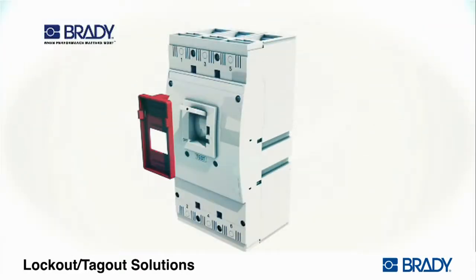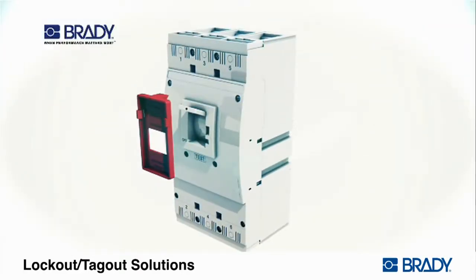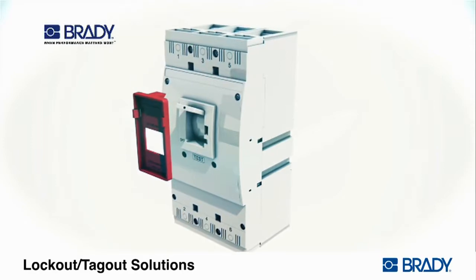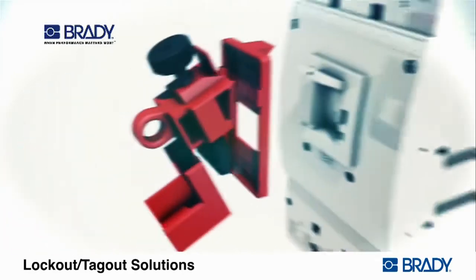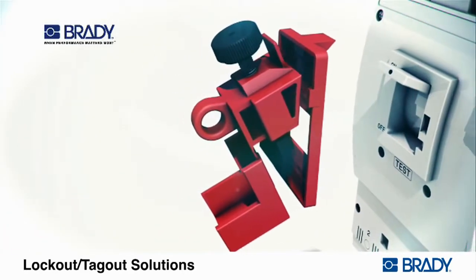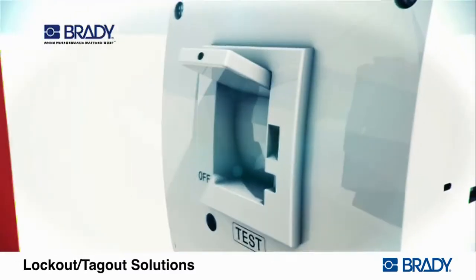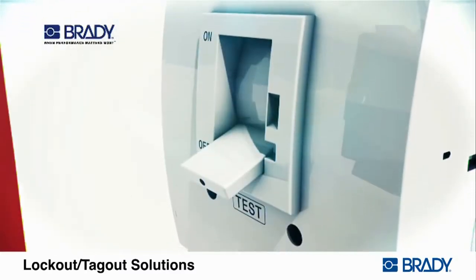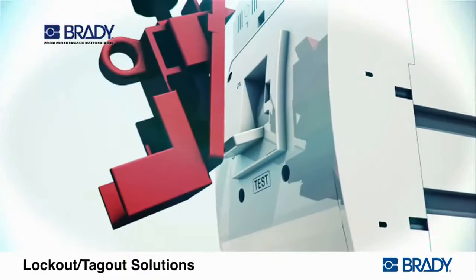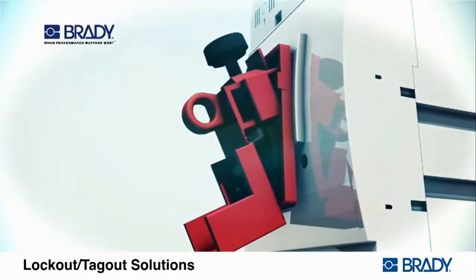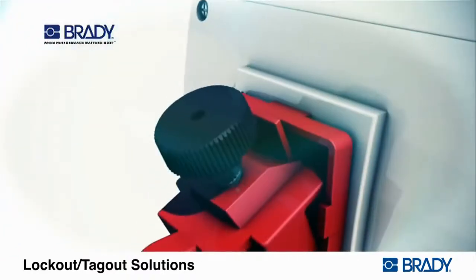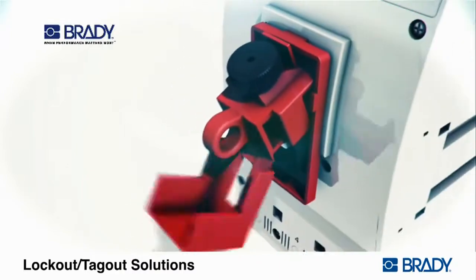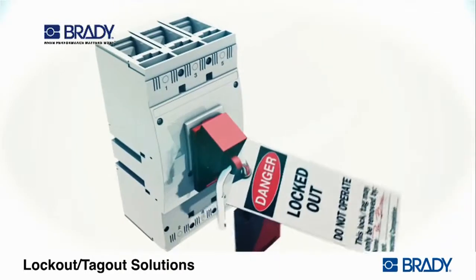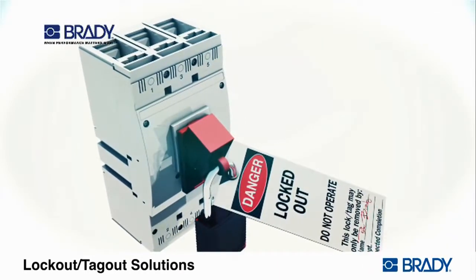Lockout cleats are used with lockouts for circuit breakers with long, sliding switch throws. To start, snap the locking cleat to the base of the circuit breaker lockout device. With the circuit breaker in the off position, install the cleat and lockout device with the cleat in the recessed area of the circuit breaker. Rotate the front wheel clockwise to secure the lockout device to the switch tongue. Attach the padlock with worker's tag.